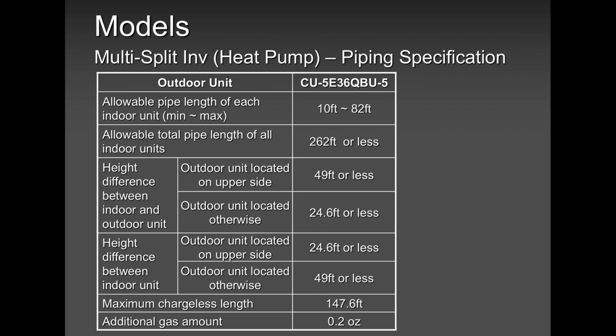because that oil protects that compressor, cools the winding from overheating. And when that oil comes back from the indoor unit, it cools the winding. And that cold vapor that comes back from the indoor units keeps the compressor cold. So always keep in mind, guys, if the unit says don't exceed 82 feet, do not. In this case, 82 feet per indoor unit. Guys, we're talking about multi-zone. So 82 feet per indoor unit.